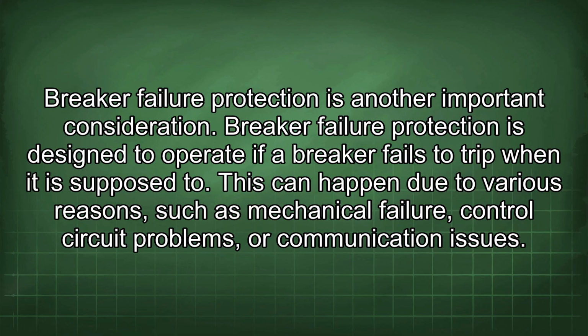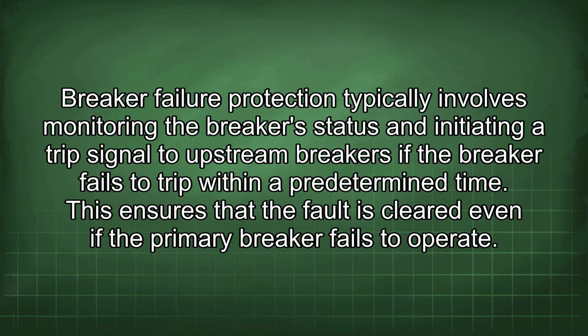Breaker failure protection is another important consideration. Breaker failure protection is designed to operate if a breaker fails to trip when it is supposed to. This can happen due to various reasons, such as mechanical failure, control circuit problems, or communication issues. Breaker failure protection typically involves monitoring the breaker's status and initiating a trip signal to upstream breakers if the breaker fails to trip within a predetermined time. This ensures that the fault is cleared even if the primary breaker fails to operate.